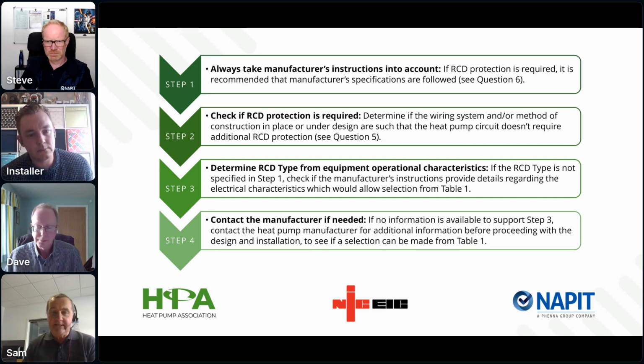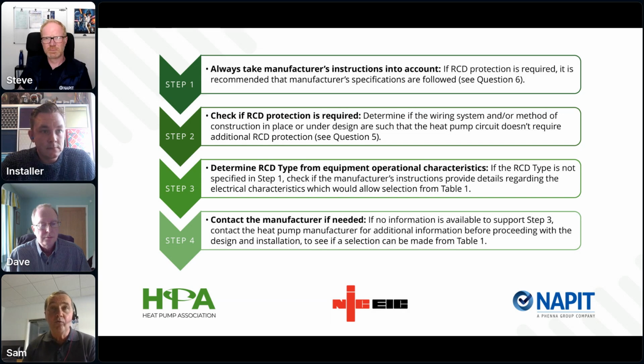Now, that's for a number of reasons. As Dave said, because sometimes manufacturer's instructions aren't as detailed as are required for the electrical installation side. And there's also situations where the manufacturer's instructions are sometimes behind wiring regs because they were written a long time ago, and sometimes they're ahead of wiring regs because BS 7671 also goes through cycles. So it's because BS 7671, the wiring regs, are there to cover all the specified types of electrical installations. It's not specific to heat pumps, which is why it says take account of manufacturer's instructions.